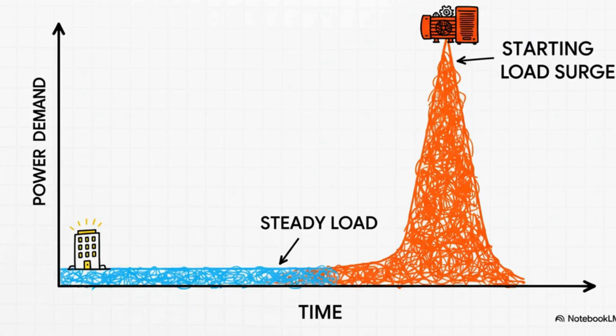And that's because the real challenge for a generator isn't the steady running load. No, the true test, the thing that will bring a system to its knees, is the massive, instantaneous surge of power that's needed to start big equipment, especially those huge motors in things like elevators and air conditioning systems.